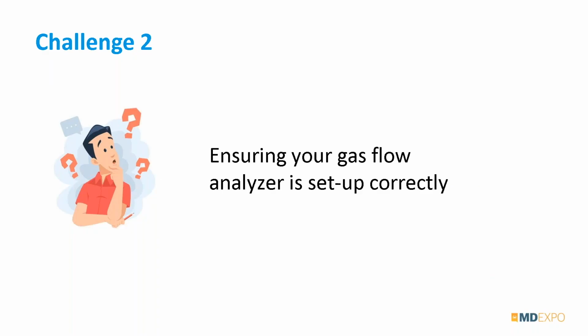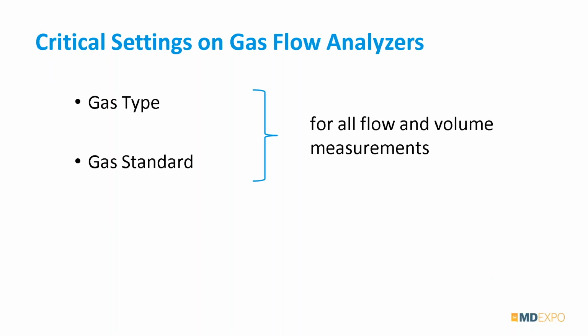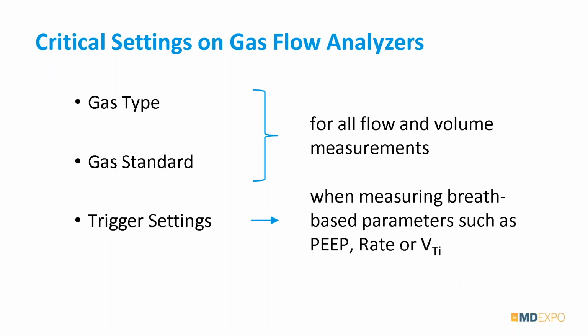Now, something that might help you in that is to know how to set up your analyzer correctly. Okay. There are critical gas settings on all the analyzers that you should know and be familiar with. Okay, there's something called gas type. We have gas standards, and those are both used for flow and volume measurements. And then we have things like trigger settings that are used for breath-based parameters, things like rate, tidal volumes, PEEP settings, things like that. We'll go through each one of these and show you and talk about each one.